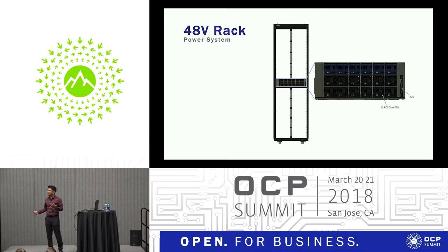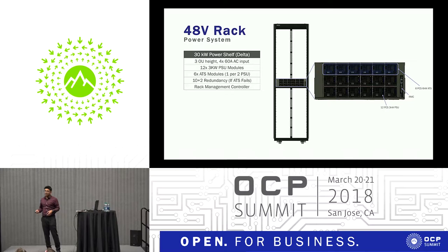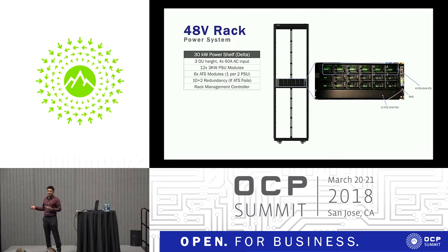So one of the blockers for Rackspace to consume 48 volts as is, was an absence of an automatic transfer switch solution. So we've partnered with Delta to build an ATS, an in-built ATS power shelf. We have the ATS samples here as well. So that's a picture of the actual ATS in one of our labs. You can see all green stuff, so everything's good, hopefully, right? So we have that picture. So we basically have this ATS working, and it's, I think, one of the first implementations with the integrated ATS, and that really helps us take the 48-volt rack and just plug it in our data centers and go. So you have the power shelf.